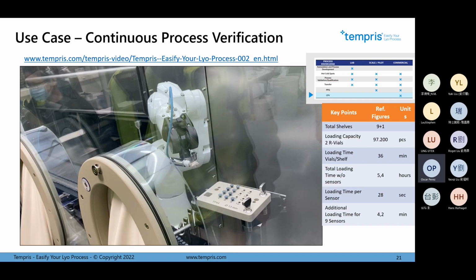But in the single lines, we have to stop the line, remove the stopper, and put in the sensor. This robot is able to replace the stopper and put in the new one with the sensor in only 28 seconds. So this is a very short time, we keep the loading line stopped for just 28 seconds for every sensor. I'm sure that will not affect the product, since some products are very sensitive to temperature and have to be loaded immediately into the freeze dryer.